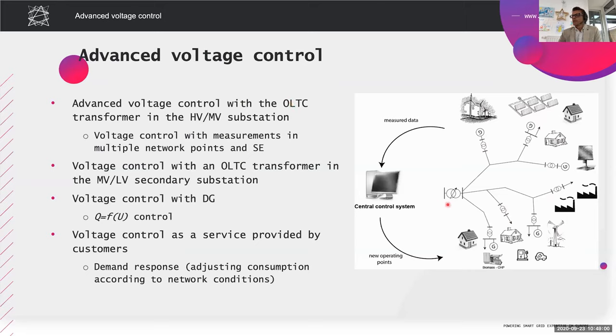So what is the advance here? Instead of measuring the voltage only here in one network point, you can measure the network voltage in multiple network points. And in this way, you can control the voltage much more precisely. And of course, you have much more freedom on how to set the voltage. The other, a more expensive solution, is to install also at this level, so at the transformer station from the medium voltage to low voltage, transformers with a tap changer. And this gives you, of course, much increased flexibility at low voltage level.